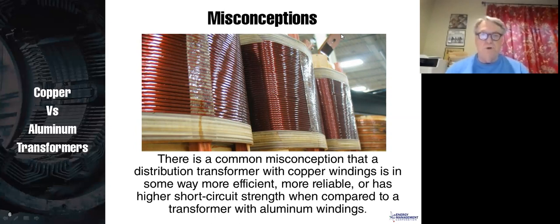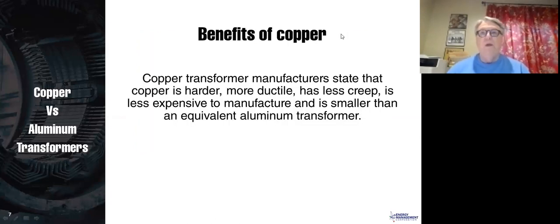There is a misconception that distribution transformers with copper windings are more efficient or more reliable, or they have a higher short circuit withstand. And so we're going to just talk about that for a moment. If you look up on the internet or you have a copper transformer manufacturer who's trying to tell you that his transformer is based on copper and therefore is better, they will generally tell you that copper is harder, it's more ductile, it has less creep, it's less expensive to manufacture, and is smaller than an equivalent aluminum transformer.